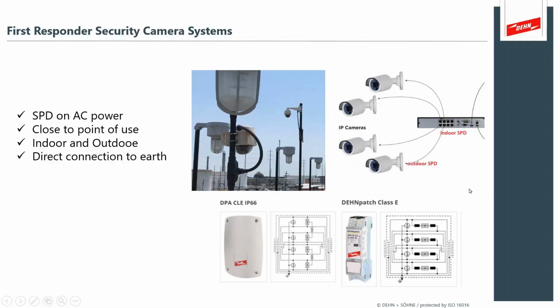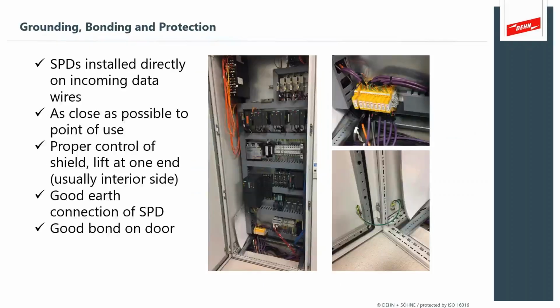And again, it's important to protect at the point of use, both ends, and grounding and bonding and protection go together as part of that overall lightning protection. What you're looking for is to make sure that the SPDs are installed correctly to the manufacturer's suggested operations. You make sure that you pay attention to shield lifting on your data circuits. You want to make sure that you have that good door earthing bond.